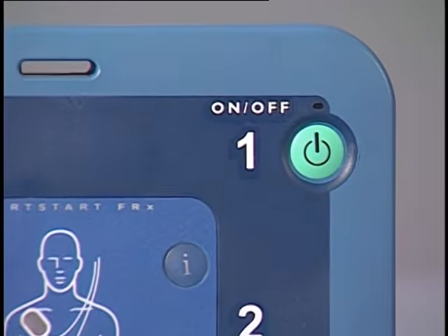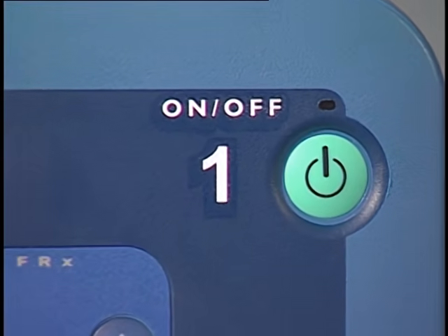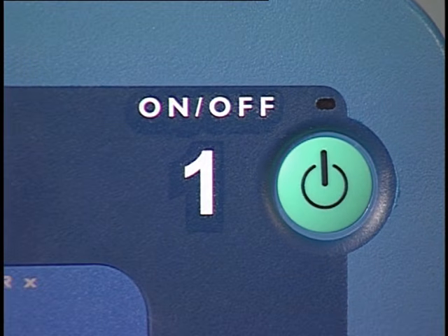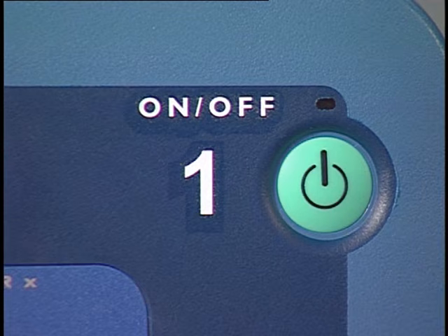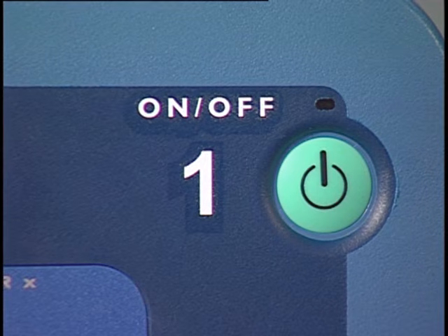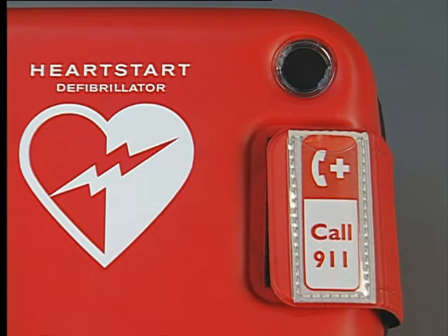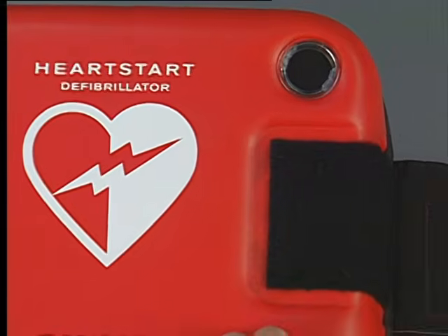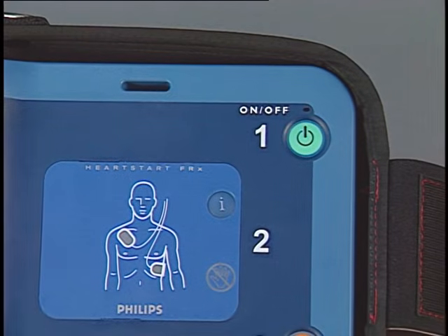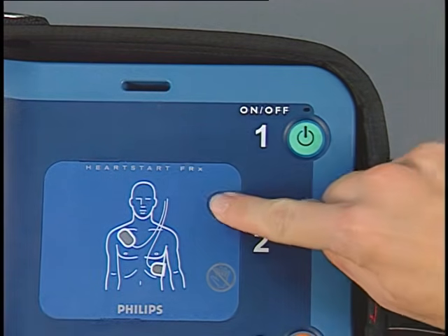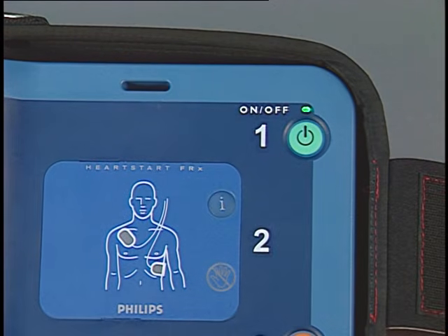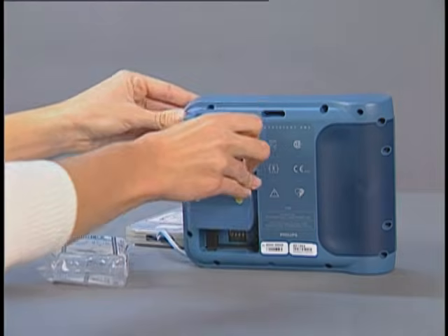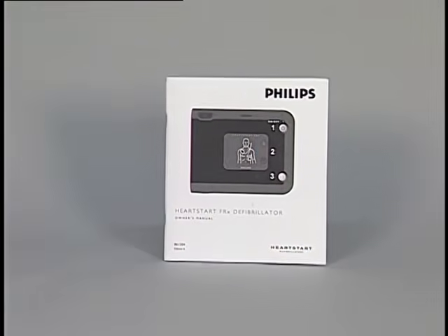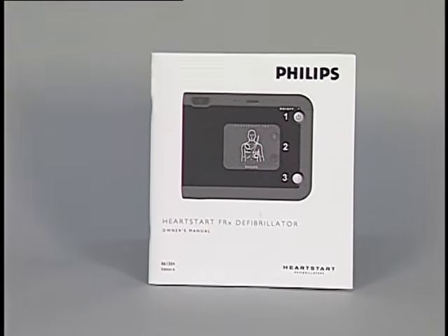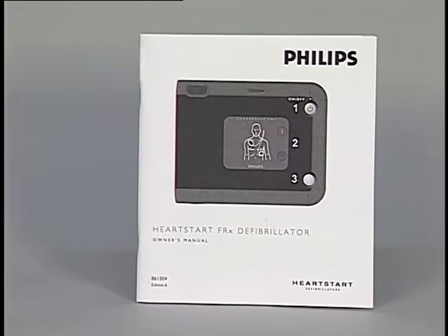As long as the Ready Light is blinking and the FRx is not chirping, you can be confident the defibrillator has passed its most recent self-test and is therefore ready to use. If the Ready Light is not blinking and the FRx is chirping, it needs attention. Open the case. The blue I button will be flashing. Press the I button for more information and follow the defibrillator's instructions. Replace battery immediately. The FRx Owner's Manual contains additional information on maintaining and cleaning the FRx.